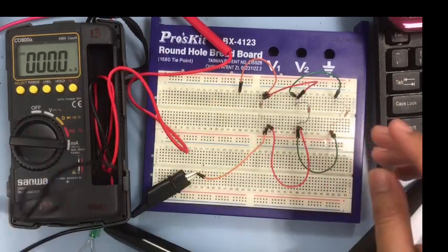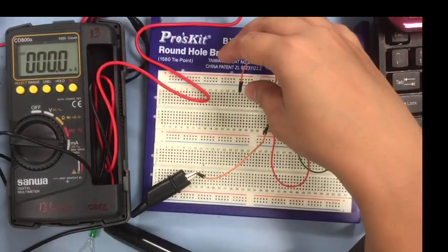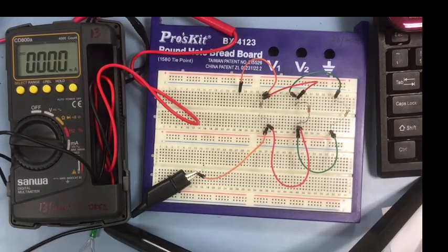Right? Now we want to measure partial voltage. Okay, test point DK, FK, and HK. I think I should do the test point DK, FK, HK first, for voltage.